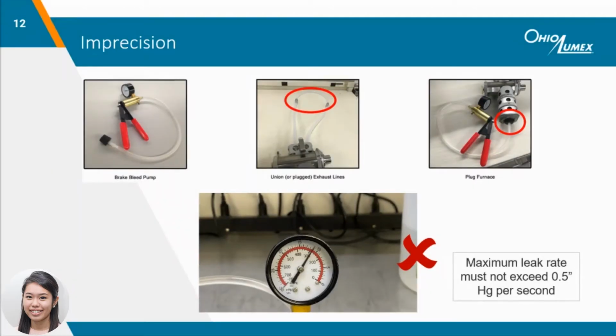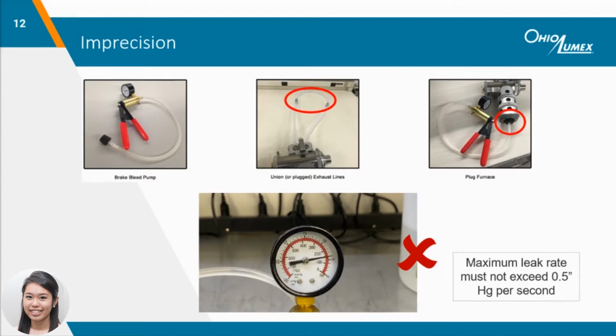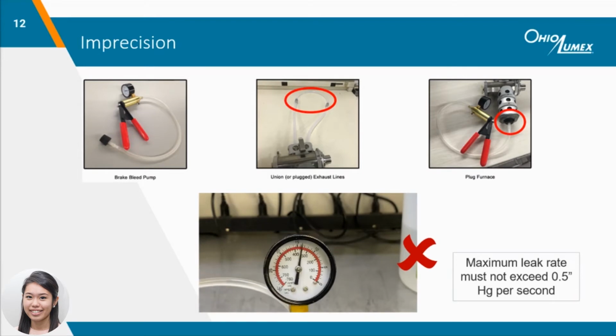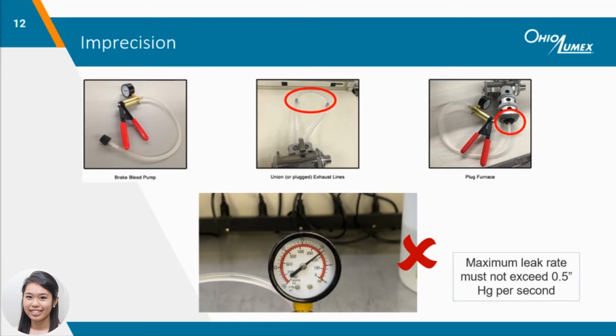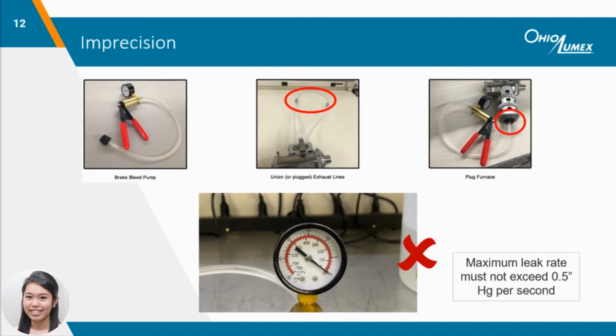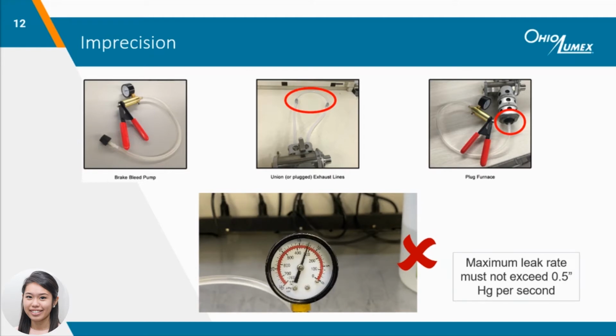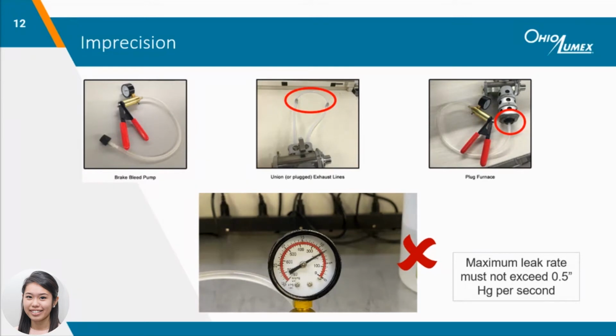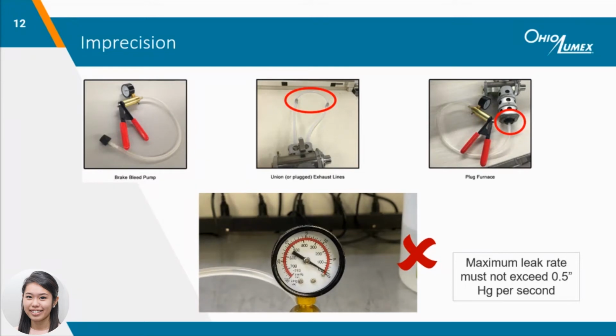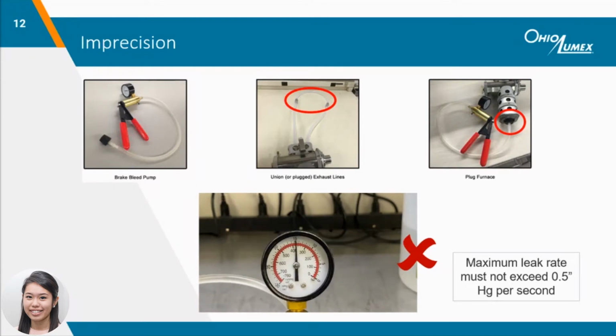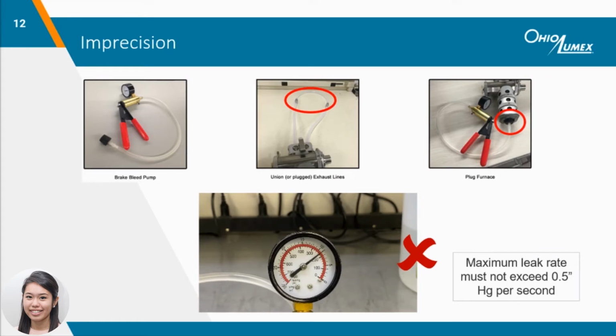The M324 leak check kit includes a brake bleed pump with a vacuum gauge, which makes it easy to adjust the tightness of the window collars while verifying the vacuum. Make sure the furnace attachment has cooled down to ambient temperature prior to performing a leak check. Use the Quick Connect union in the M324 leak check kit to isolate the cell chamber and plug the opening of the furnace using the hand pump.